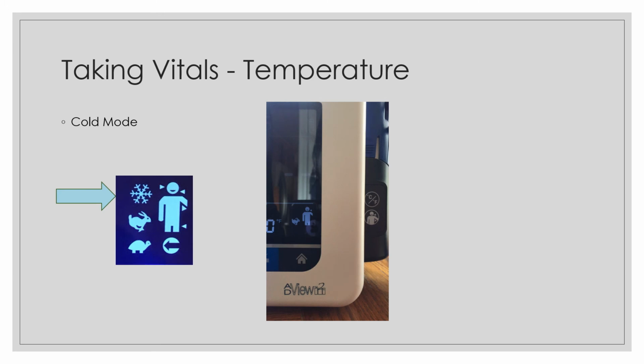Let's discuss cold mode. If you have a patient who will be predictably having a lower temperature, for example, a hypothermic patient in the field, the unit will anticipate and obtain a quicker, more accurate reading by placing the temperature probe into cold mode. Cold mode is indicated by the snowflake next to the person icon. To switch the ADView2 into cold mode, depress both buttons simultaneously. The icon will change from quick mode to cold mode. To return to quick mode, repeat the action.